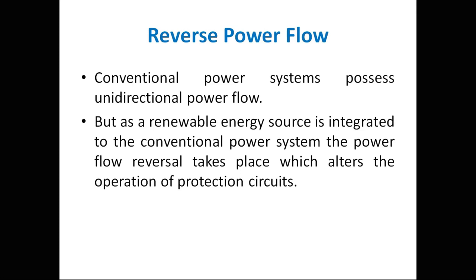Regarding reverse power flow: conventional power systems have unidirectional power flow — no customer sends power to the grid. But in a renewable energy power system, the consumer may give power to or take power from the grid, making it bidirectional. This alters the operation of protective circuits. For example, relays or circuit breakers must now be made bidirectional — protecting current flow from A to B or from B to A.